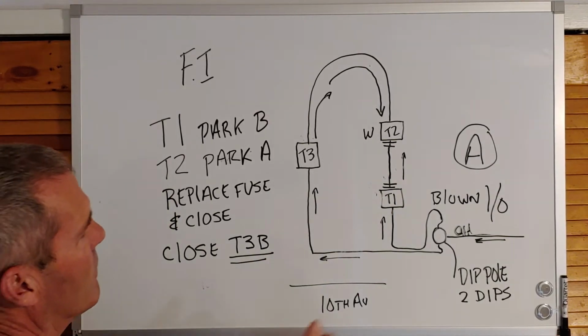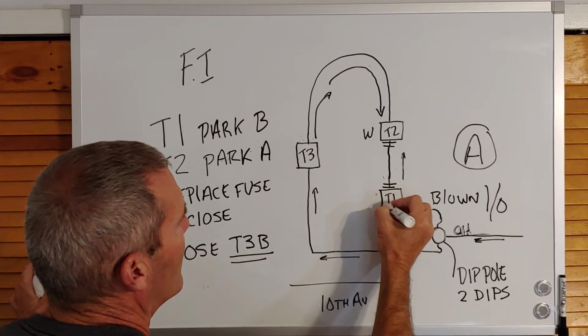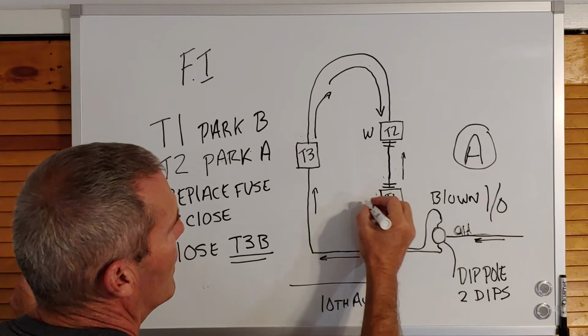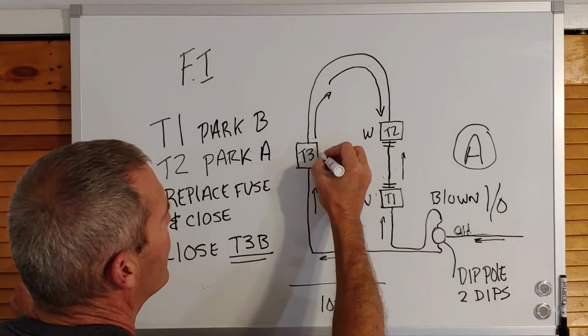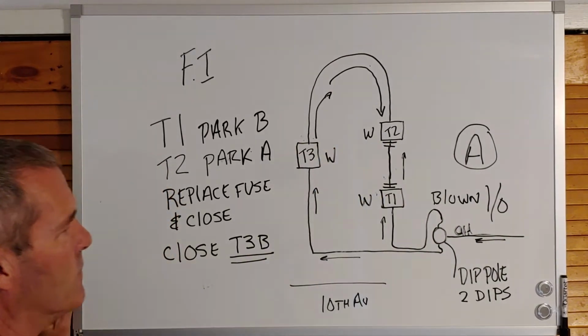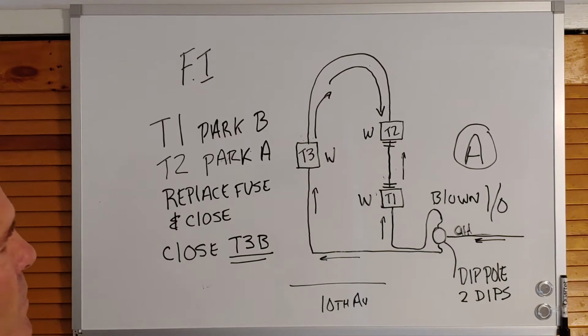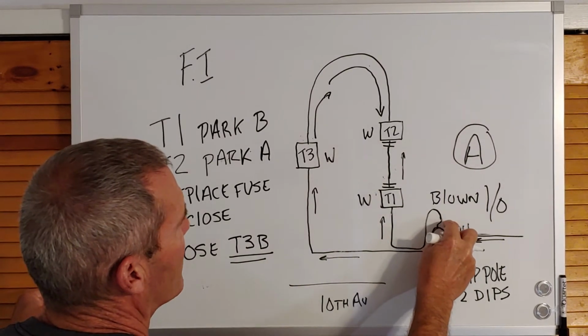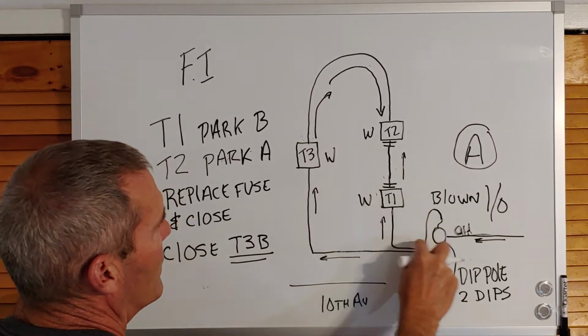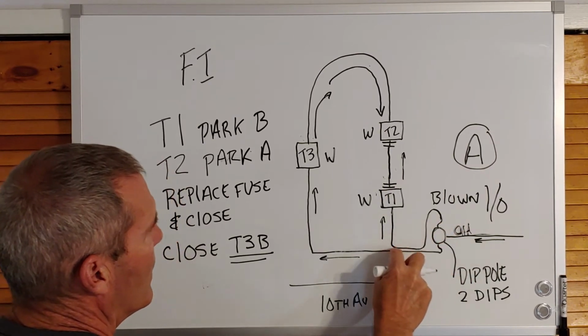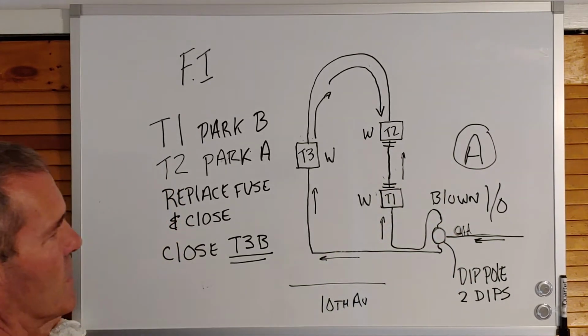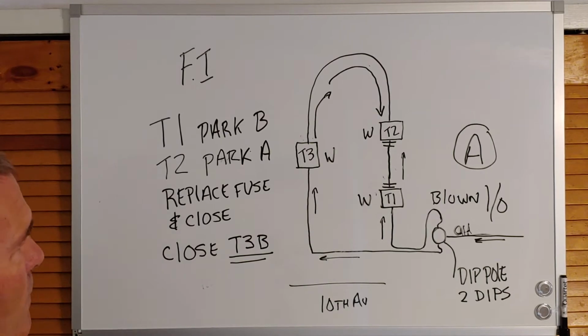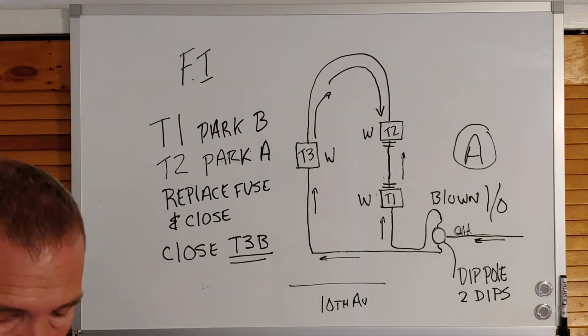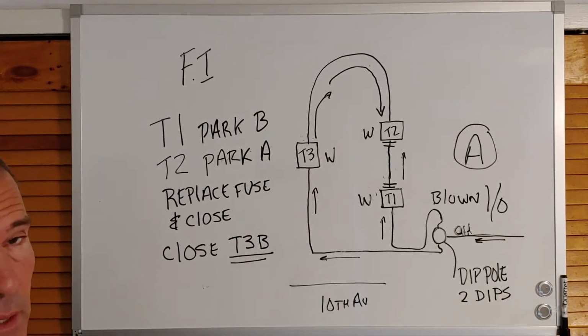Just to go back for a moment to give you that scenario. I drive in. This fuse is blown. I have white, white, and white. We know immediately this is my first fault indicator right here. The fuse is blown, meaning I have a bad span between the dip pole and the first transformer. Let me get some erasing going on. It will let you know.